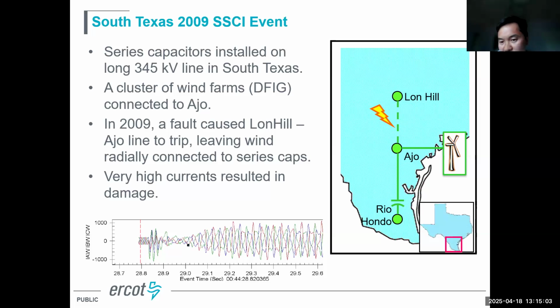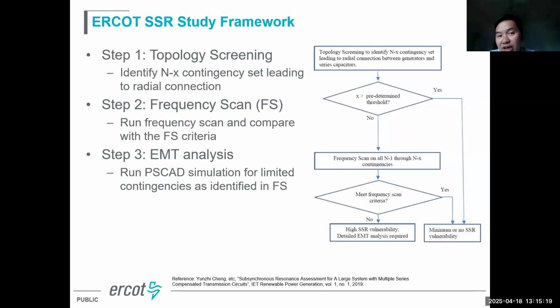So this is the first event. As I said, this event really triggered not only the industry, but also the research community to try to understand the phenomenon, like why we have these issues. So then in ERCOT, since we have a lot of series compensation, we proposed a study framework, which is a 3-step study framework. We first run topological screening to identify the contingencies, which we call N-x, that could lead to radial connection. Because based on our experience, radial connection is the most challenging or conservative condition for SSCI.